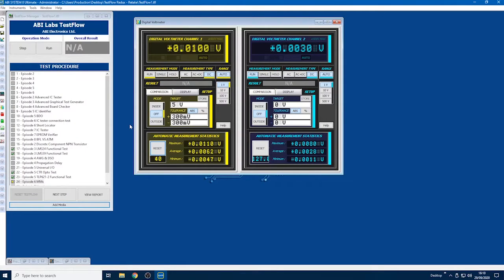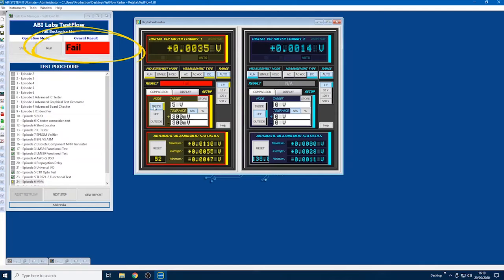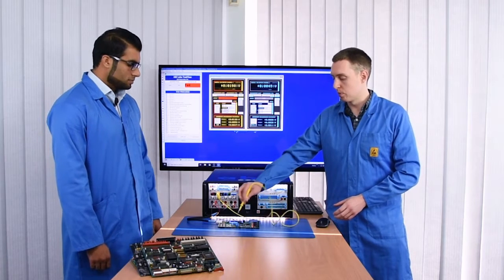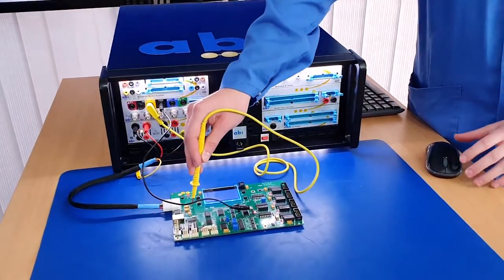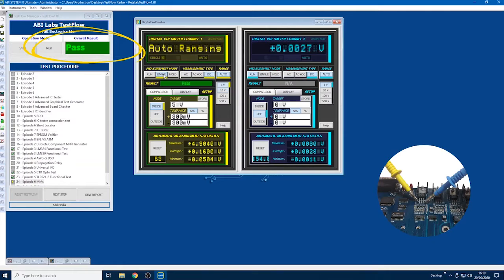As it's running already, I'll take my tolerance inside my target. Of course, I'm measuring zero volts at the moment, so I'm going to get a fail. But once I actually measure the point I'm looking for, I'll get a pass. I'll take a single measurement so I can release the probe.